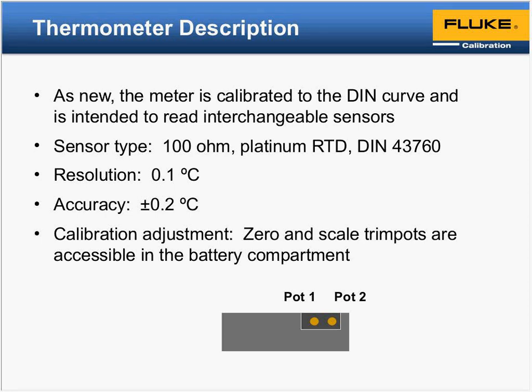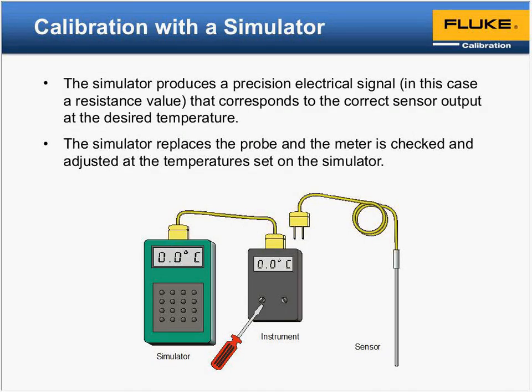Basically, the adjustment. In this scenario, the unit or the readout piece has a trim pot 1 and 2. Basically, that's a 0 and a high trim pot that we're going to be looking at to adjust. So in this picture, it's showing what we're going to be doing here. So the rough drawing here, but in this scenario, basically we disconnected the probe portion or the sensor piece from the readout piece, and now we plugged in the simulator. In this scenario here, we've got it connected and we're simulating 0, and now we're not going to make the adjustment yet, but the screwdriver represents the trim pot 1 where you would make the adjustment.